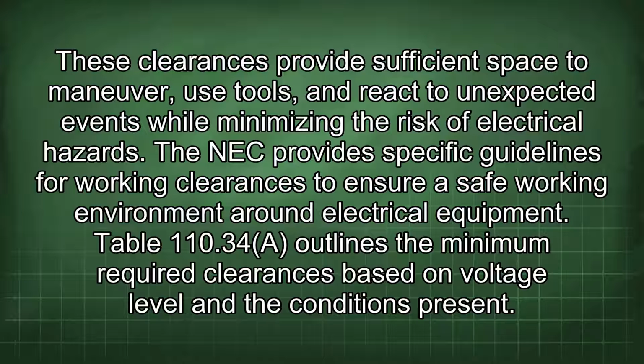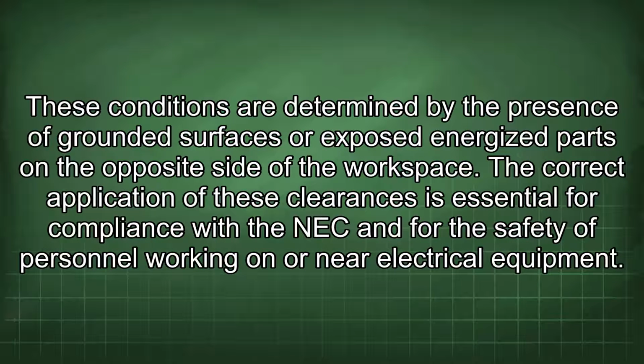The NEC provides specific guidelines for working clearances to ensure a safe working environment around electrical equipment. Table 110.34 outlines the minimum required clearances based on voltage level and the conditions present. These conditions are determined by the presence of grounded surfaces or exposed energized parts on the opposite side of the workspace. The correct application of these clearances is essential for compliance with the NEC and for the safety of personnel working on or near electrical equipment.